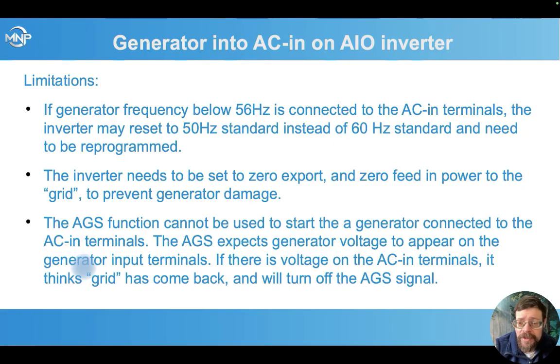So newer firmwares, this shouldn't be a problem, but also make sure your generator, if you're connecting a big generator, has good frequency control on it. Most of the bigger ones do, but some small ones vary all over the place, especially some of the cheaper ones. I've seen them drop into even the high 40s for frequency under heavy loads when you can hear that engine bog down.